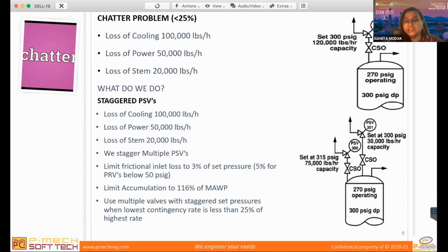And even if you see the set pressure, of PSV 301, I set at 300, whereas this PSV 300, I set at 315, which is more than this. So first, whenever loss of steam happens, this PSV will open. And on loss of power, both the PSVs will open because the pressure keeps on rising. So first 301 will relieve and then 300 will start when 315 reaches.